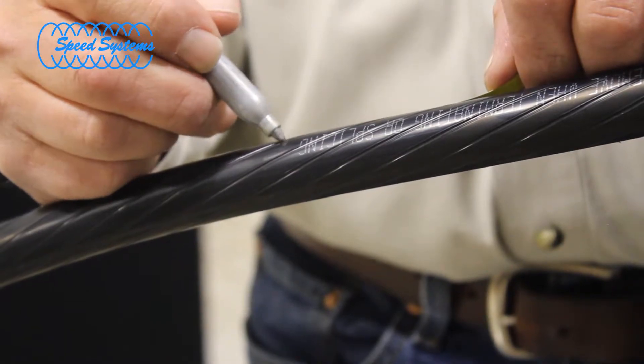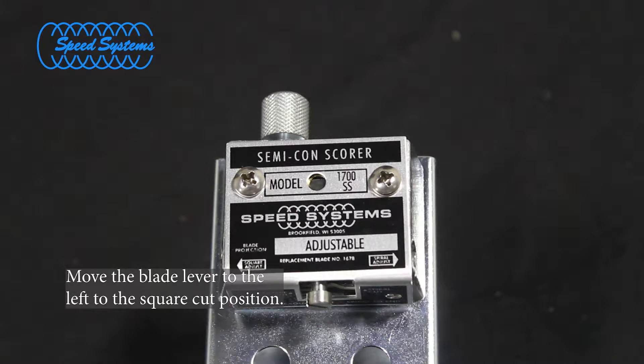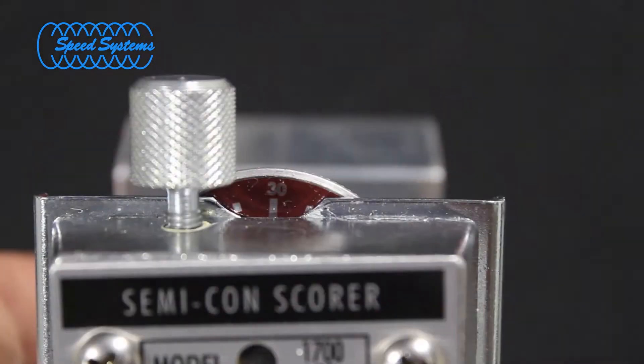Measure and mark the SEMICON strip back according to the component manufacturer's instructions. Verify that the blade lever is in the square cut position and set the SEMICON SCORER blade depth to cut through most of the SEMICON layer without cutting through to the insulation.